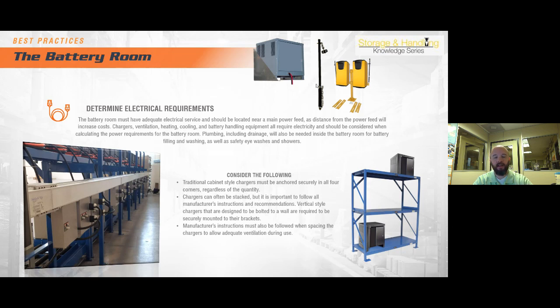It's very common to see forklifts hit these types of cables, damage them, damage the connector on them, or even, in a changeout type system, the cable dangles and then gets pinched by the battery itself against the racking.